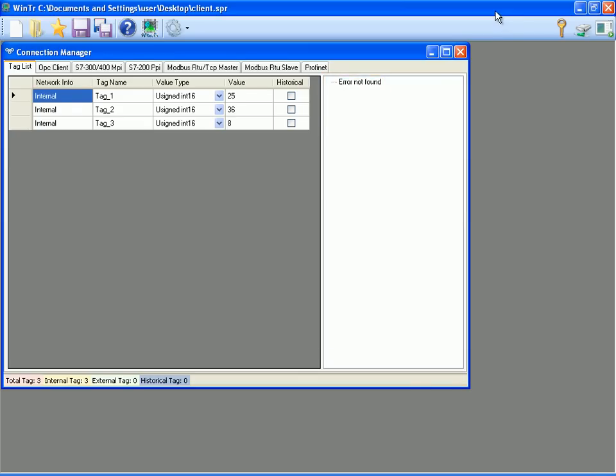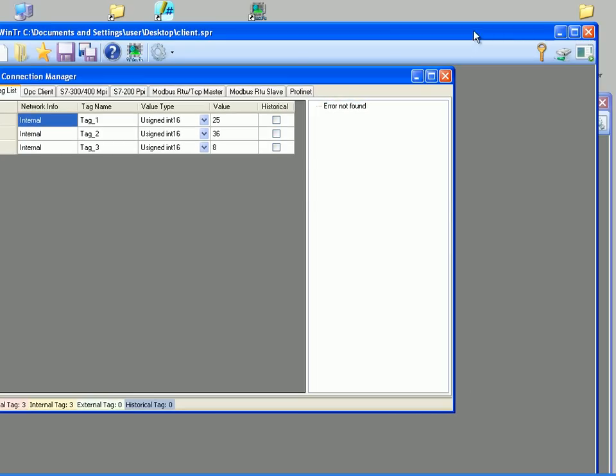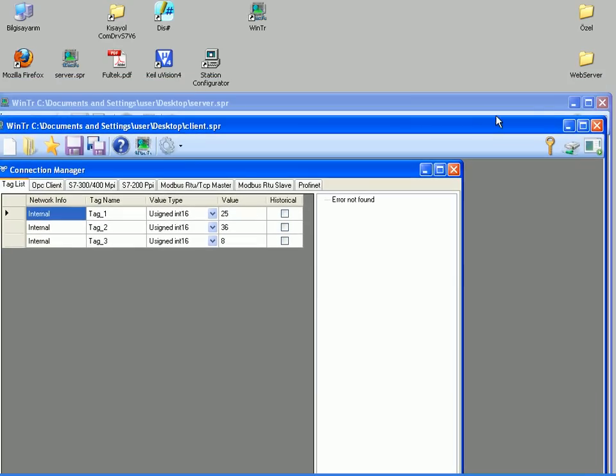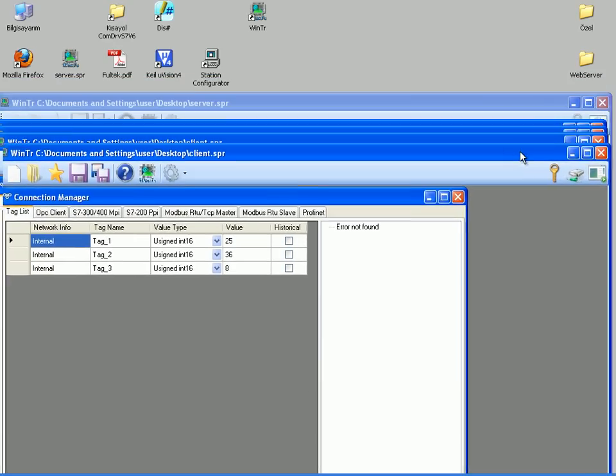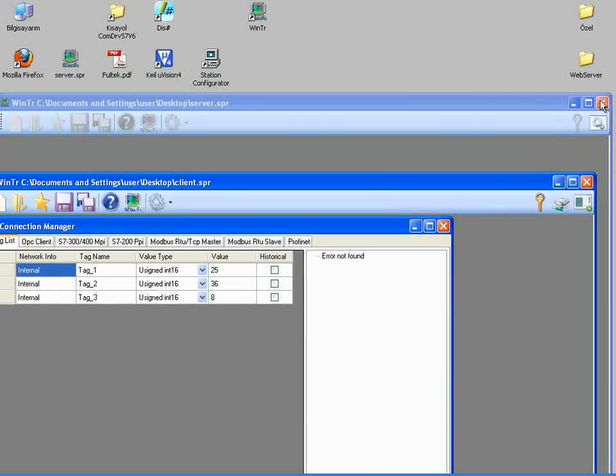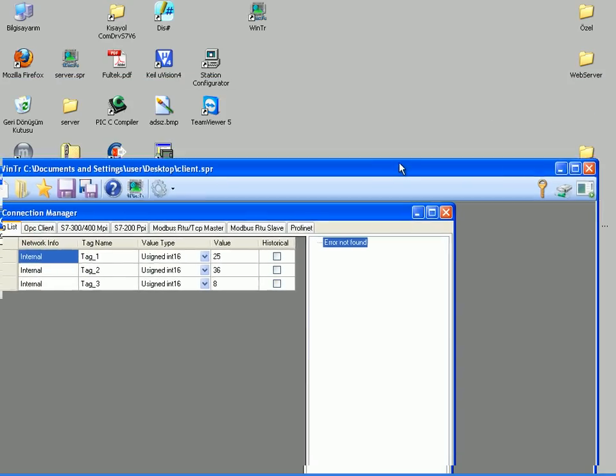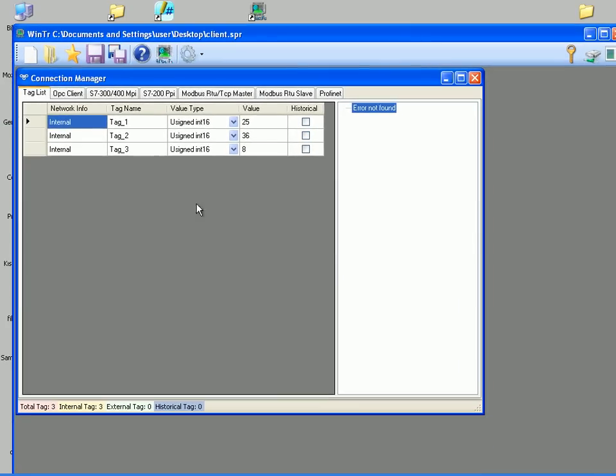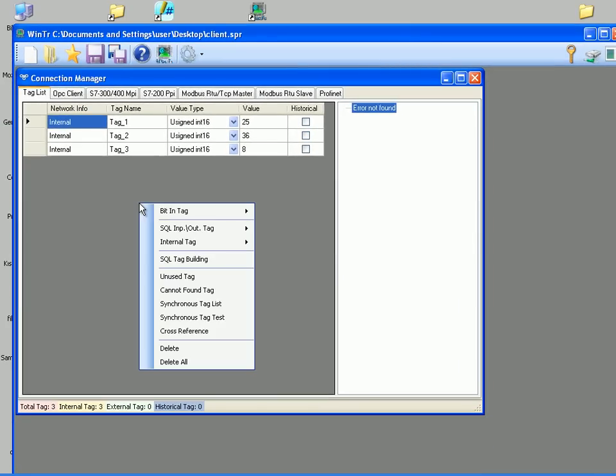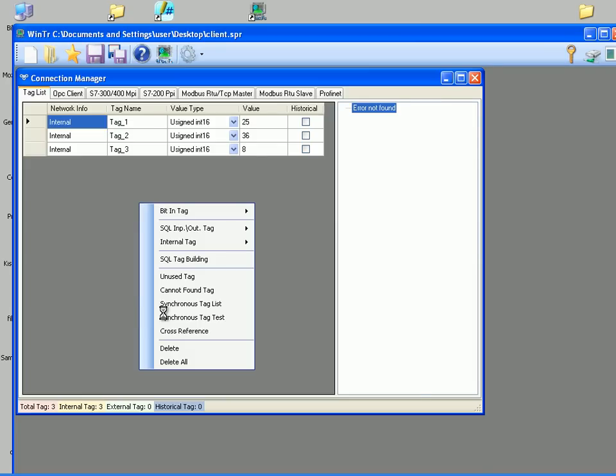To get this feature more clearly, let's close the server project. And click again on synchronized tag test. It's trying to connect the server for a while and displays a message that server cannot be accessed. This message indicates that because the connection cannot be established, the server is disabled. If this warning appeared when switching to runtime, SCADA wouldn't try to connect the server again in that session. If server will be up at the next runtime startup, everything will be okay.